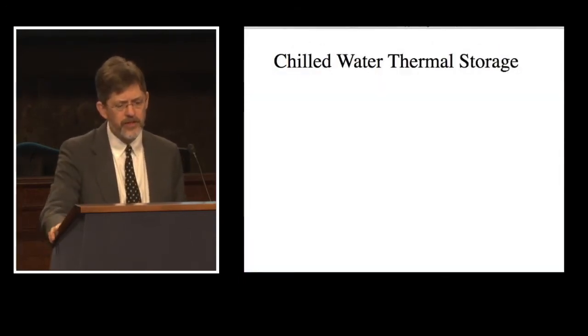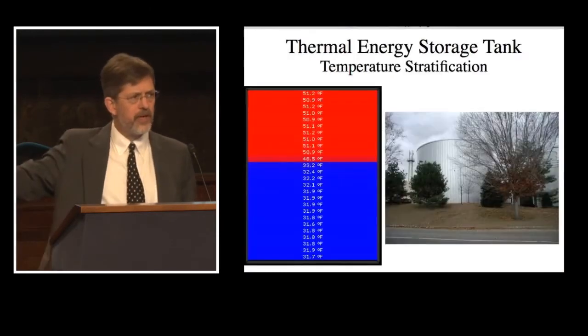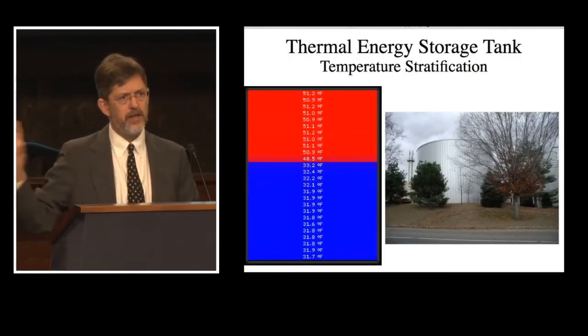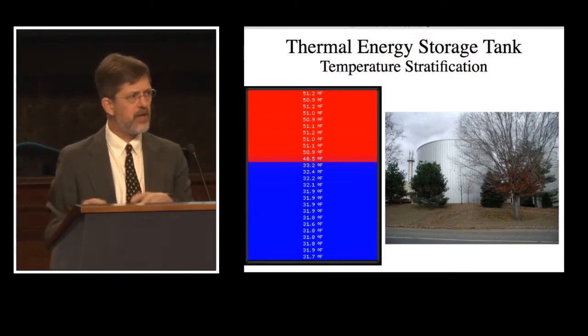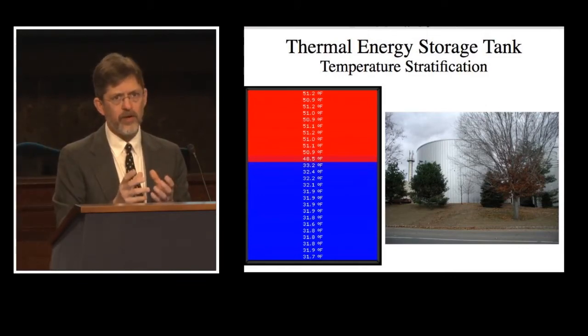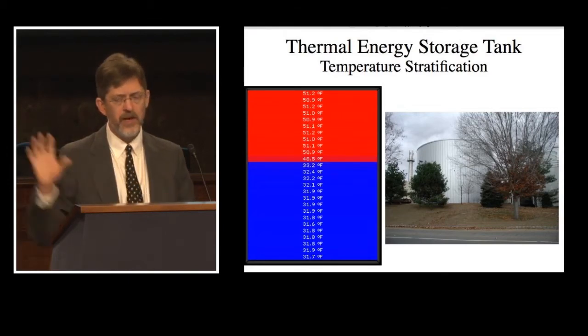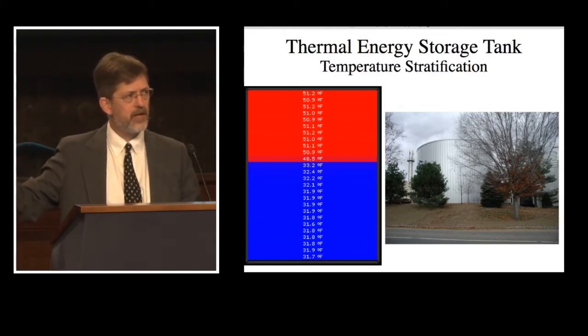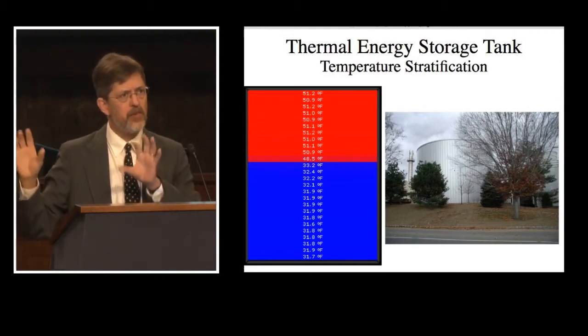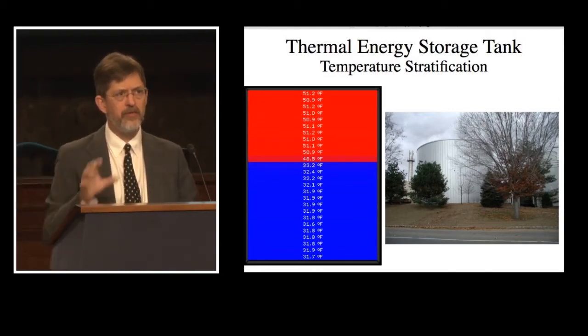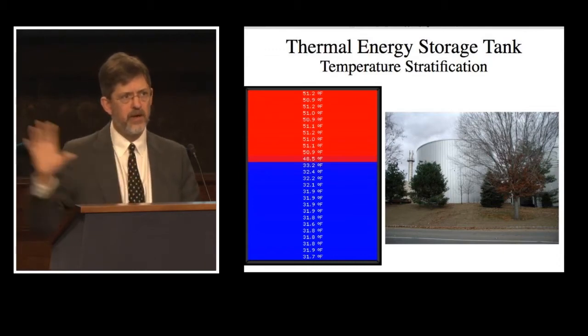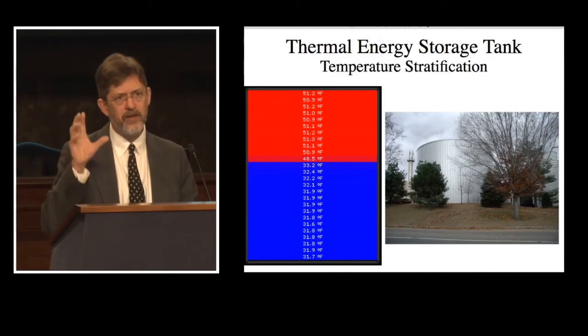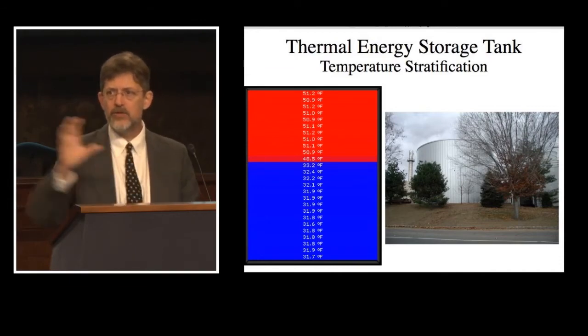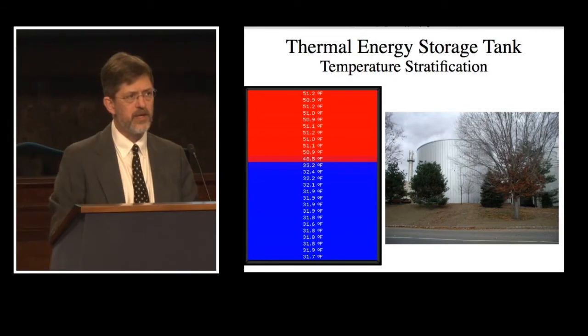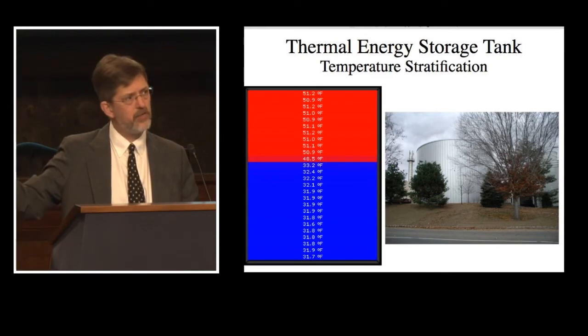Again, thermal storage, we've got the chiller decoupled from the campus needs. So the chiller and campus needs are now decoupled in time, so I can operate the chiller whenever power is inexpensive, and meet campus needs whenever the campus wants it. We've decoupled the moment of production from the moment of need, and decoupled the problems in the plant from the campus customers. By having energy storage, you separate the problems from the customers, and you're able to buy energy when it's least expensive and deliver it when it's most valuable.